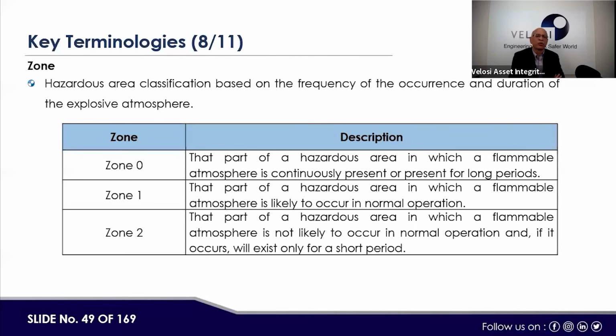Now we go to the zones, which we normally discuss. As per IP-15, zone 0 is the part of a hazardous area in which a flammable atmosphere is continuously present or present for a long period. Like zone 0 is inside the fluid. If a tank is filled with diesel, kerosene or any other hydrocarbon, zone 0 would be applicable, and any electrical equipment installed inside the tank should meet the requirements of zone 0.